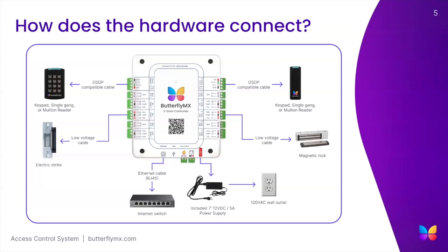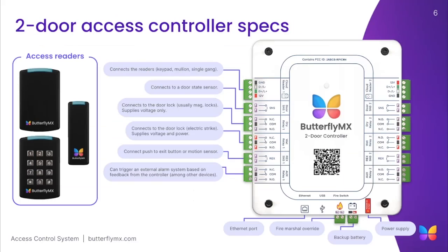Let's get into a couple of features that are supported by the two-door access controller. The first being a fire relay input. If you have a fire alarm control panel that provides a signal, you have the option of connecting the fire alarm system to the two-door access controller to automatically unlock all of the doors and gates connected to the controller. An additional feature is a battery backup that can be introduced to protect against any power outages, terminated to the battery backup relay on the two-door access controller.